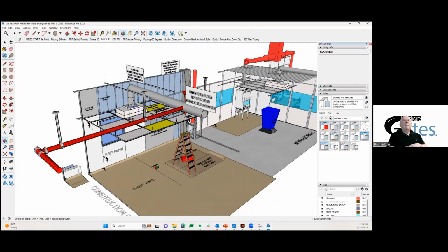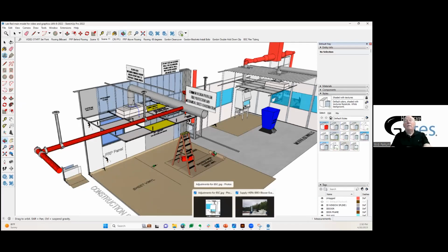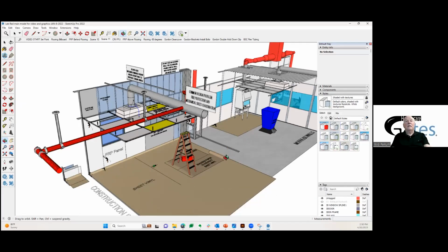Okay, so we have this environment in which you're going to put hoods, and there are all sorts of descriptions for them depending on the layer of cleanliness you need. But all rooms have a certain amount of what's called ISO air requirements, air cleanliness. The minimum that you have would be a clean room, or anything that has nothing to do with hazardous, and that's a USP 797 room.